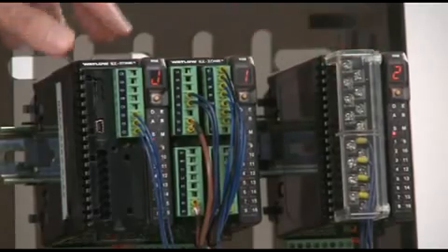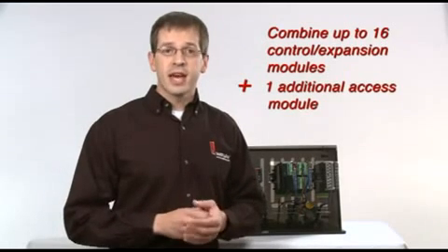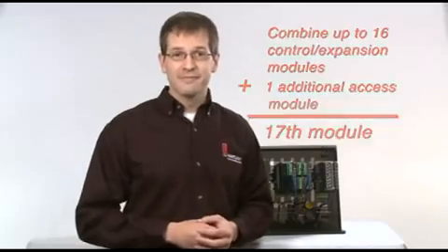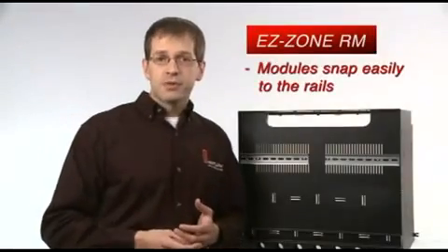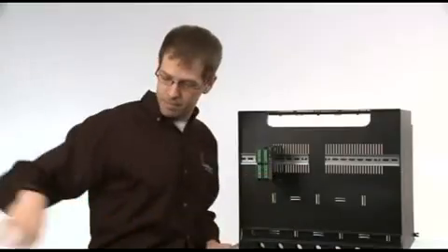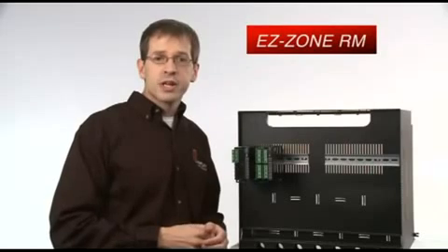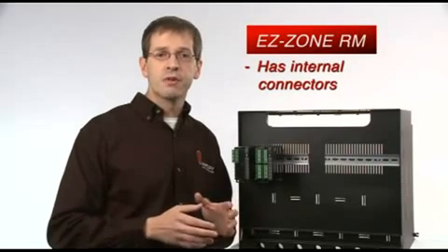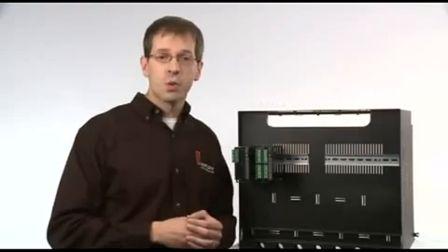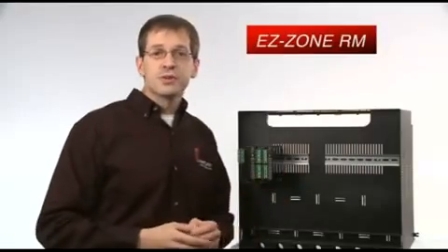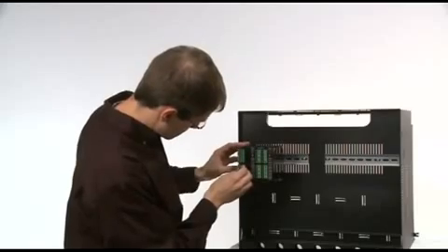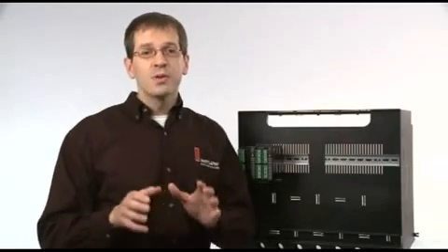There are 3 modules in the EZ-ZONE RM family: a control module, an expansion module, and an access module. With the EZ-ZONE RM, you can combine up to 16 control and/or expansion modules in any configuration, plus 1 optional access module, which gives you communications and data logging capability, thus making the 17th module. To mount the modules, simply snap them to the rail. This product has internal connectors that allow modules to communicate at a system level by simply pushing them together on the DIN rail with no additional wiring needed. These modules are scalable from 1 to 4 loops. It's as simple as adding a connector to add an additional loop. So the great thing about that is you only pay for what you need.